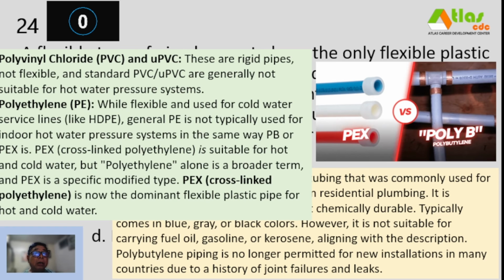So polyvinyl chloride, PVC, and UPVC are rigid pipes, not flexible, and standard PVC, UPVC are generally not suitable for hot water pressure systems. Polyethylene or PE, while flexible and used for cold water service lines like HDPE, general PE is not typically used for indoor hot water pressure systems in the same way PB or PEX is. PEX or cross-linked polyethylene is suitable for hot and cold water, but polyethylene alone is a broader term, and PEX is a specific modified type. PEX cross-linked polyethylene is now the dominant flexible plastic pipe for hot and cold water.